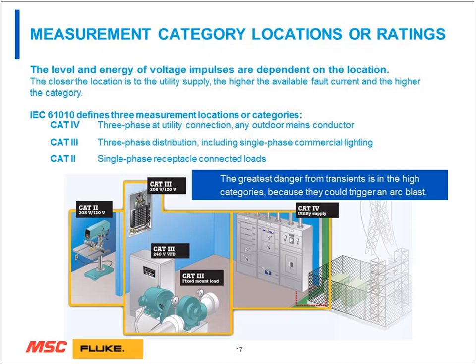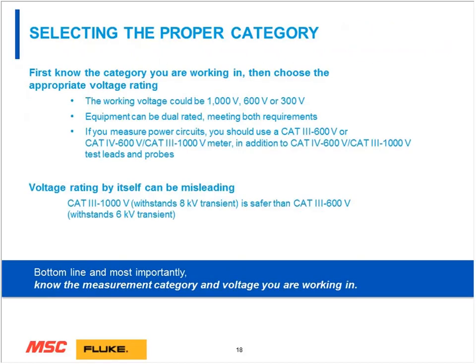As you work your way into the building, for instance, category 3, that's for three-phase distribution and single-phase lighting systems. That is an environment that by the time it makes it to category 3, some of that energy has already dissipated in other components. Then once you travel further into the building structure and you come to single-phase plug-in loads, that's considered to be a category 2 environment. So you always want to check what category your equipment is designed to work in, and you need to select the proper category.